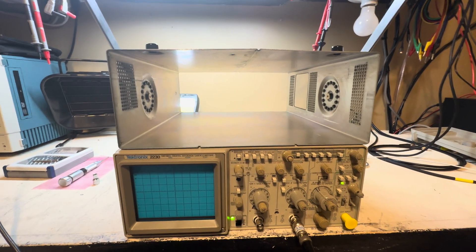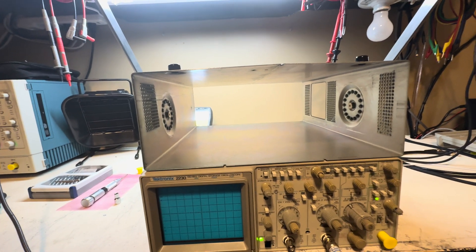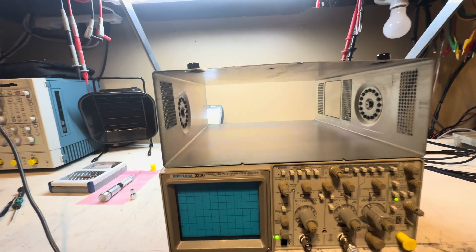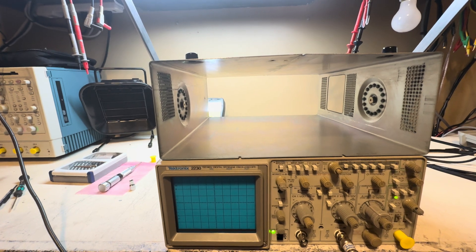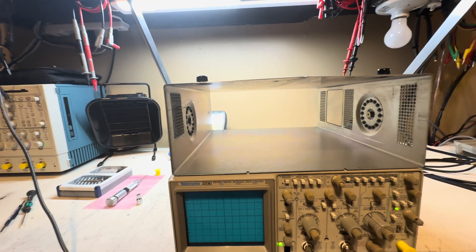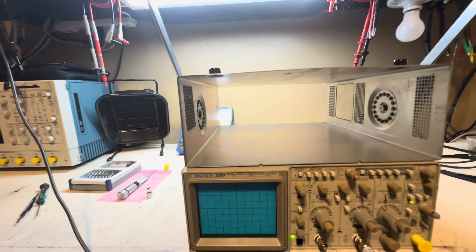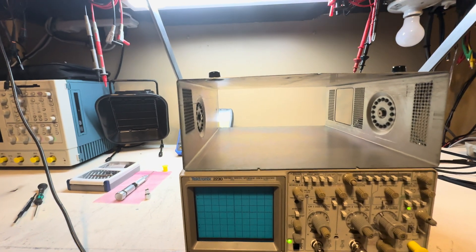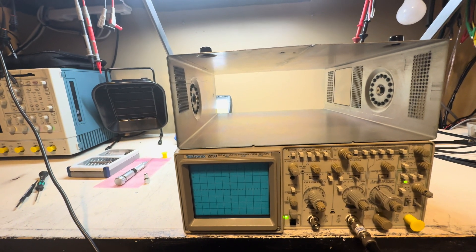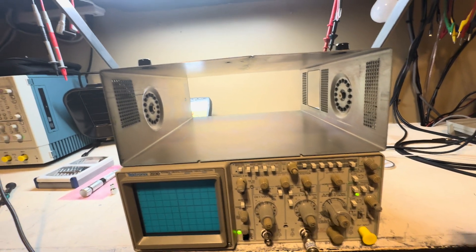The last common mistake I see — and it's critical — is that people let the scope warm up with the cover on, no fan blowing across it. On this particular model it's not a problem, but on the 2400 series with lots of ASICs and amplifiers on the bottom side of the board, you have to have the case removed. The problem then is the rear fans aren't providing airflow because you've removed the baffle. So when the scope is on its side vertically to access the adjustment pots, you need a desktop fan blowing across it.